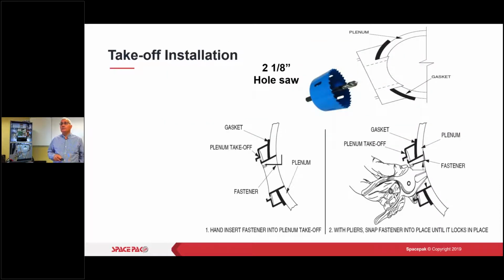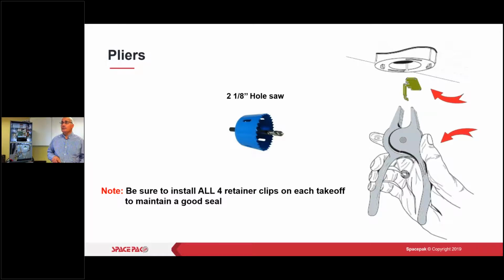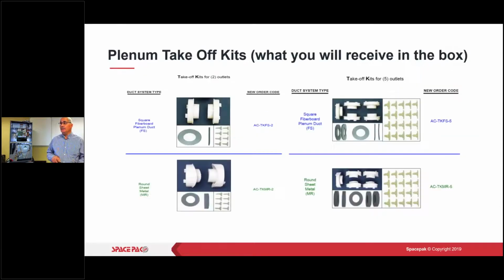All right, so if you've never done this before, you need a 2 1/8-inch hole saw. And then we snap our coupling on there, and you use those reverse pliers to snap them into place. Don't use your thumbs, you're going to kill yourself. You guys have a lot of experience with this. This should look very normal to you. The reverse pliers are a big deal. You have the retainer clips, that's what's going to snap them into place and make that good seal. In our takeoff kits, we give you the gasketing, either for a flat surface or a round surface. I've been told that even if you had a flat surface takeoff on a round, if you double gasket, that would work, but always try to use the proper kit that we need.